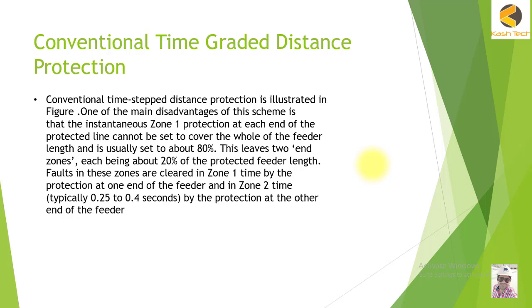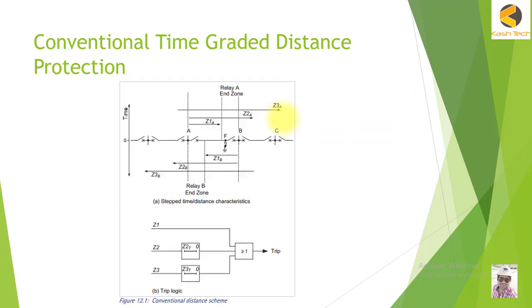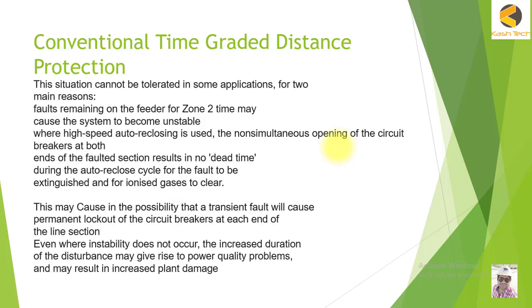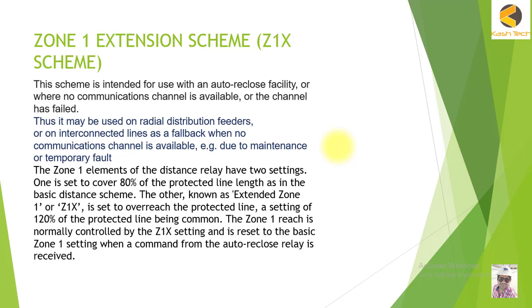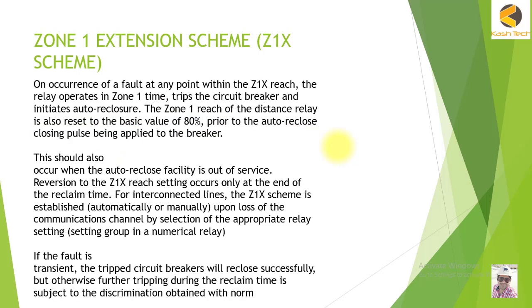We will then understand conventional time-graded distance protection — how zones are defined, how Zone 1, Zone 2, and Zone 3 are selected, and how zone tripping is done. After explaining these theories, we will study our first permissive intertrip scheme, which is called the Zone 1 Extension scheme, where Zone 1 is extended temporarily for a given time period.